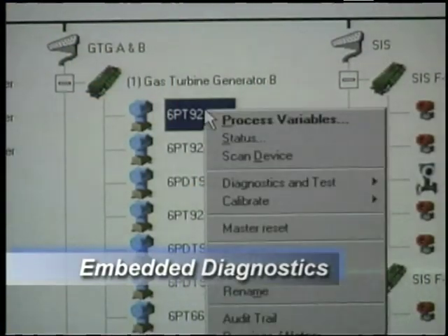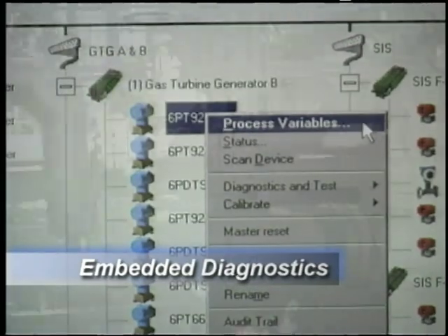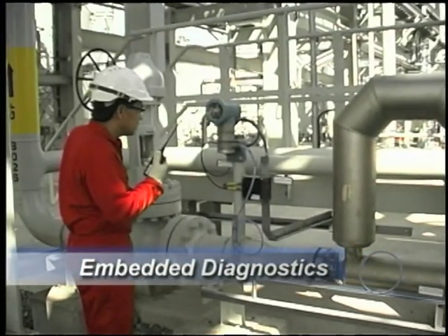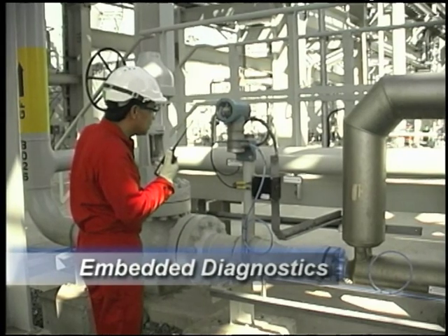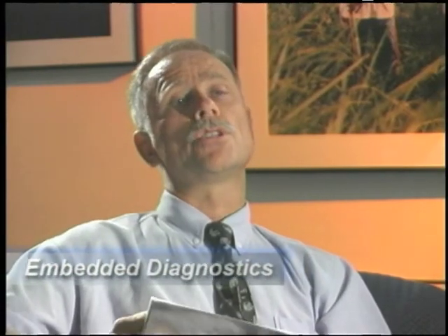The embedded diagnostics in the digital system allows Shell to contain maintenance and manpower costs while meeting its availability needs. It's mainly the feature of AMS which will enable us to do this remote diagnostics, and that's the only way with low manning to give a very early indication if there is something wrong, so you don't need to send operators to the field again and again to check the instrumentation. The AMS, designed into Delta V, is what we're looking at to provide remote diagnostics.